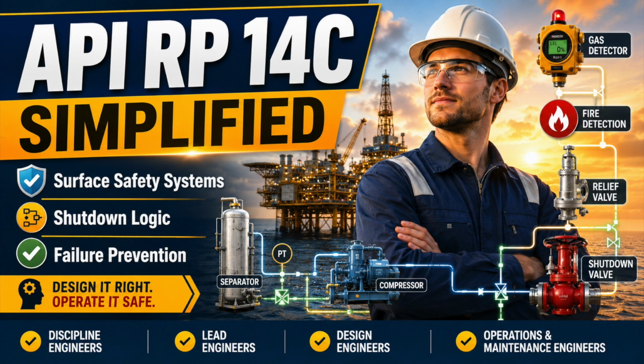Do not count layers by counting tags. Trace independence. Two pressure switches on the same impulse line can fail together. Two transmitters powered from the same vulnerable supply can fail together. Two shutdown valves controlled by the same solenoid can share one failure path. Two devices installed side by side can be lost in the same fire, impact, or corrosion event. Redundancy without independence is false confidence.